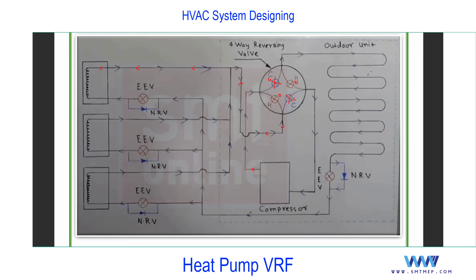In heating mode, the indoor unit's heat exchanger now becomes the condenser - we call it a heat exchanger rather than evaporator or condenser because the role can change. In cooling mode we say indoor evaporator and outdoor condenser, but in heat pump or heat recovery systems we call it a heat exchanger. The hot refrigerant at high temperature and pressure enters the indoor heat exchanger. The room temperature is low since we are using heating mode in winter, so the room air absorbs heat from the refrigerant. The refrigerant changes phase from vapor to liquid.